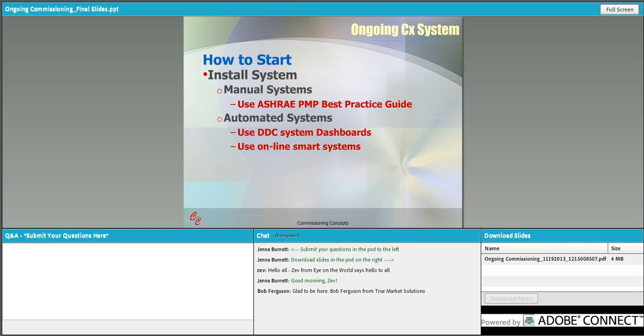Very simple. We normally use the ASHRAE PMP Best Practice Guide, which is performance measurement protocol. It's a manual that ASHRAE has produced that actually tells you how to do all the stuff, how to do these measurements, how to analyze the data, and all that is in there. Or you can have an automated system. And automated systems may use a dashboard on your DDC system, or it may use an online smart system. There are different systems that you can buy to do this.